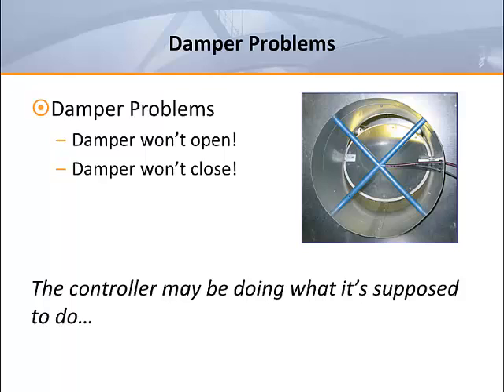On a related note, sometimes start-up technicians report that all of the dampers on a job site are full open and won't close regardless of the thermostat settings. My first response is to ask whether the air handler is running. If the air handler is off, VAV controllers will tend to drive full open because neither the minimum or the maximum airflow limit is being met. This is just the controller doing exactly what it was designed to do. This is actually a good thing about pressure-independent controls — they sit full open all night long waiting for the air handler to resume operation in the morning. That's much better than driving closed, in which case the air handler might have trouble starting due to high pressure, or could actually damage the ductwork.